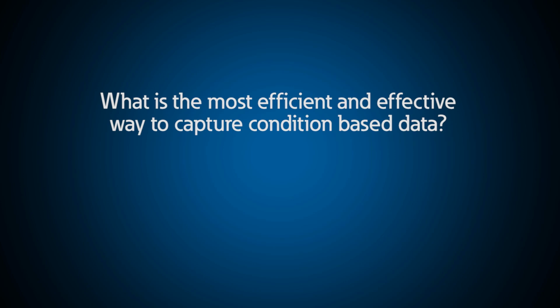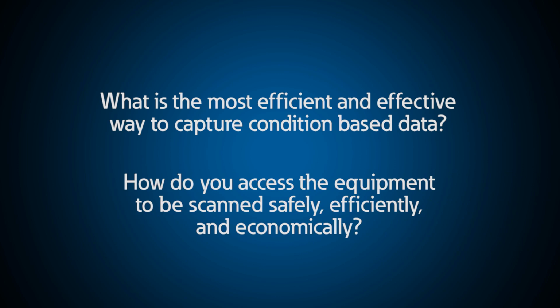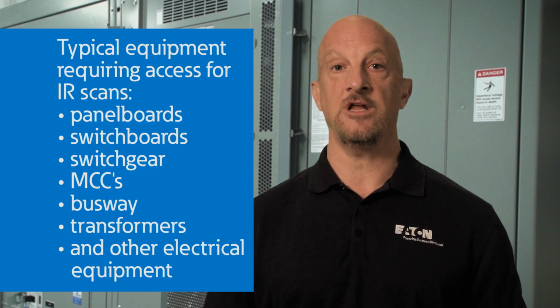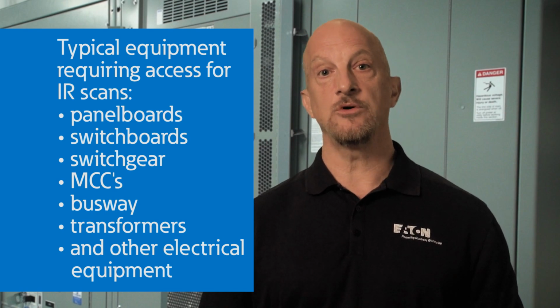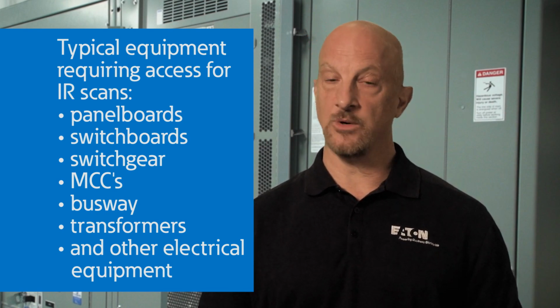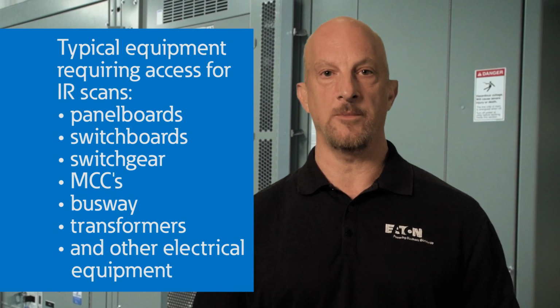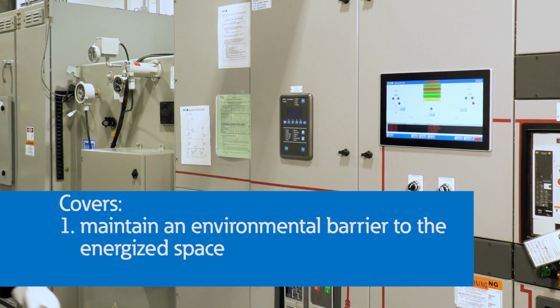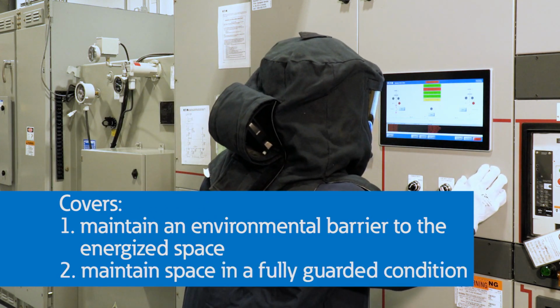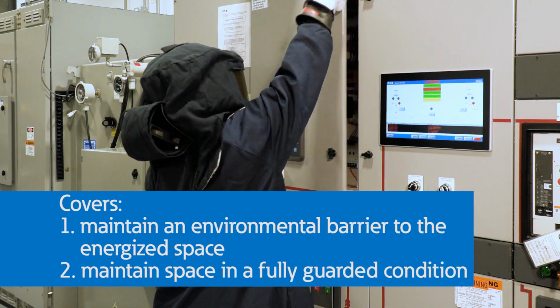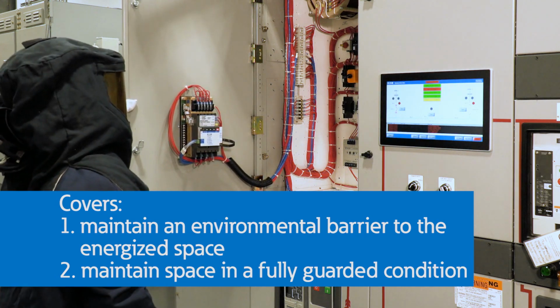The next questions that need to be answered are, if you're going to implement IR scanning, what is the most efficient and effective way to capture condition-based data that you might need, and how do you access the equipment to be scanned safely, efficiently, and economically? The typical equipment that you would need to access to perform IR scans includes panel boards, switchboards, switchgear, MCCs, busway, transformers, and other electrical equipment. The compartment covers of the equipment maintain an environmental barrier to the energized space and maintain that space in a fully closed and guarded condition while the gear is energized and operating.